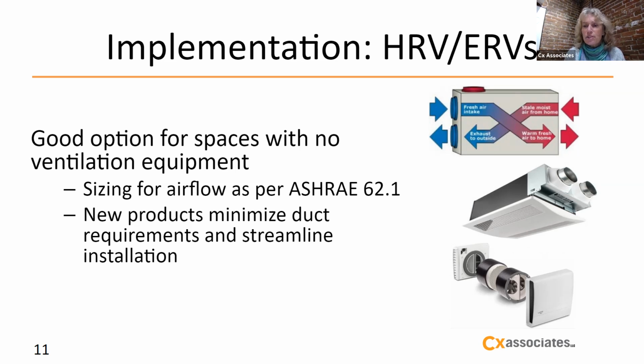The bottom picture is a through-the-wall unit that doesn't require any kind of ductwork. This is for very small areas. So say that you have a small office like I'm in right now. That is a good one where, for a certain period of time, it will exhaust air only, and it will heat up that core. Then for a short period of time, it will reverse and bring in outside air and heat the outside air with that core. And as I said, there's no ductwork. It's just a through-the-wall unit.